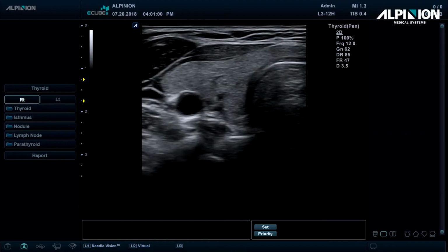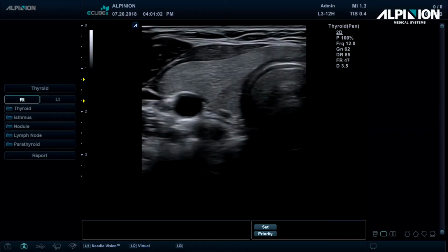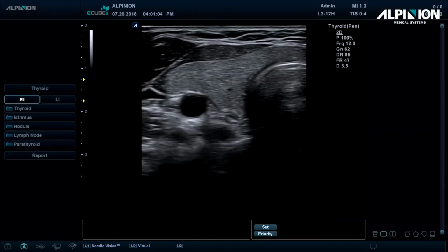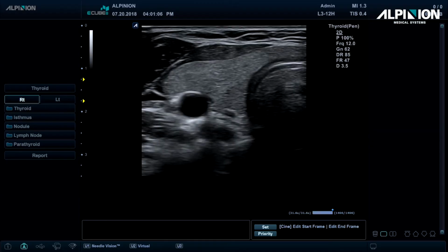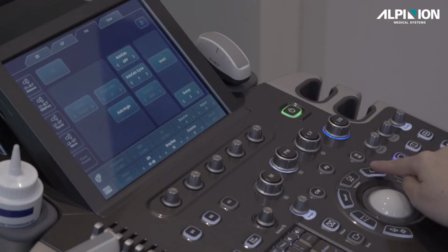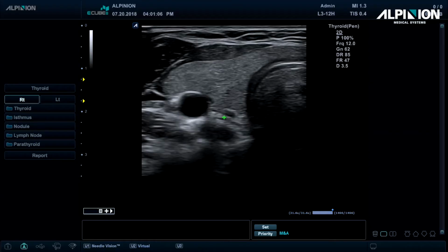Part 14. Basic Measurement. After obtaining the image, if you'd like to simply measure the distance, first press Freeze button and press Measure nearby your trackball. Then place your caliper on the start point with your Set button and drag it. And at the end point, press Set again to fix it. The measured value will be shown in the result window.